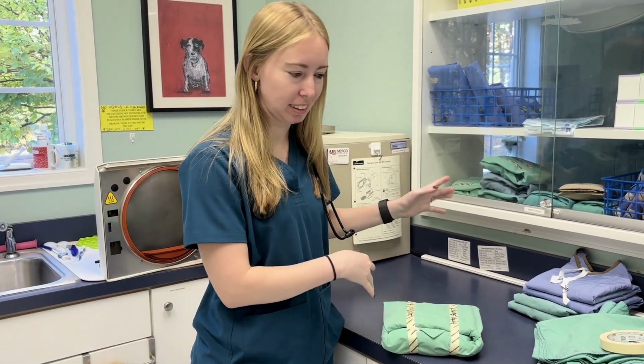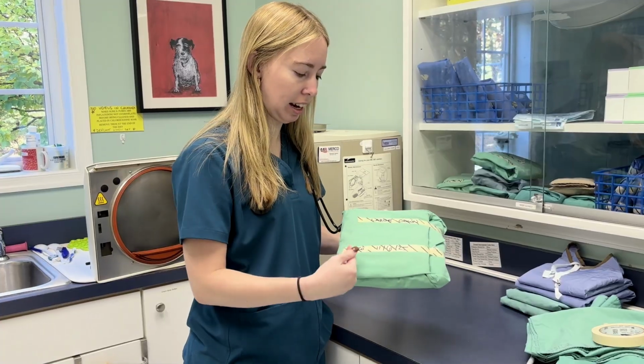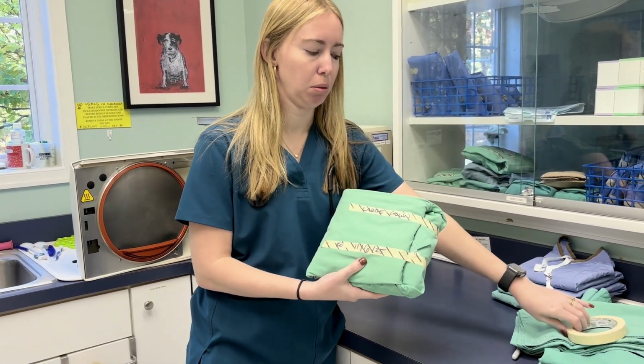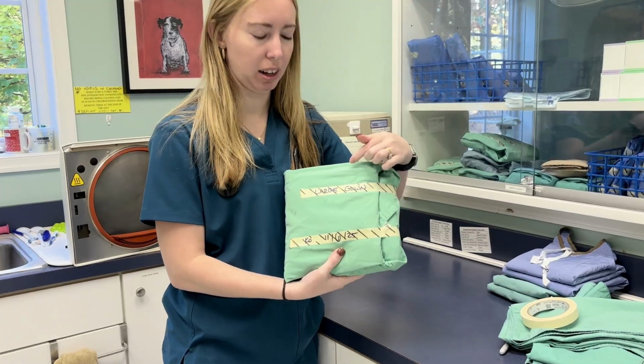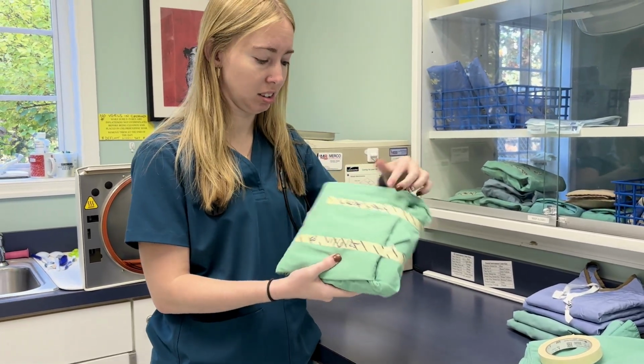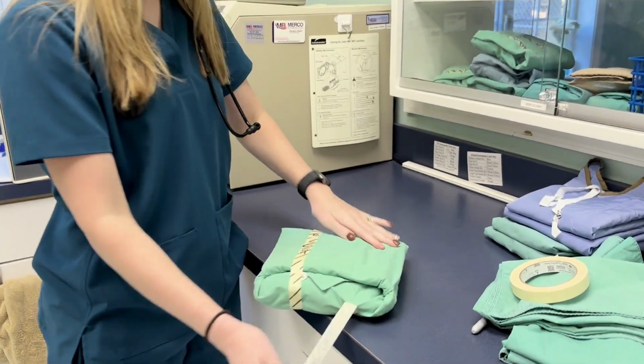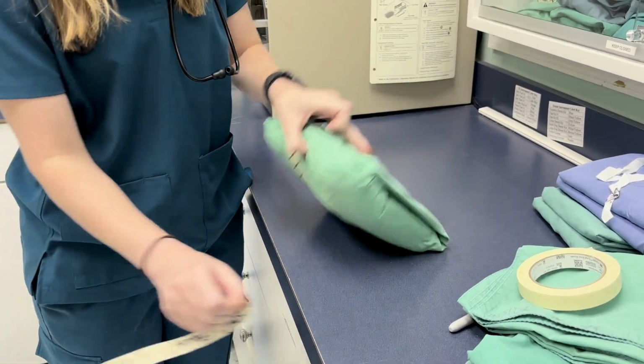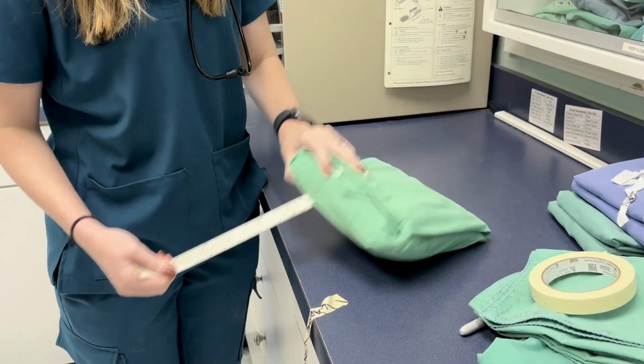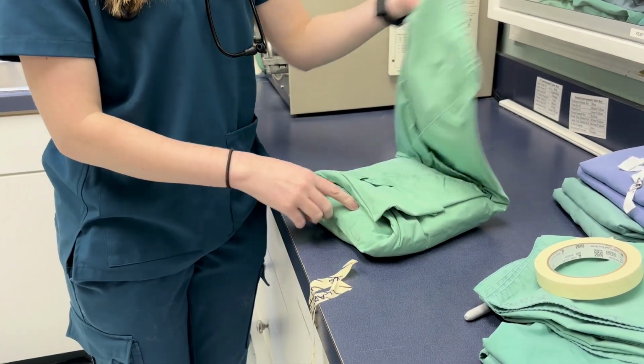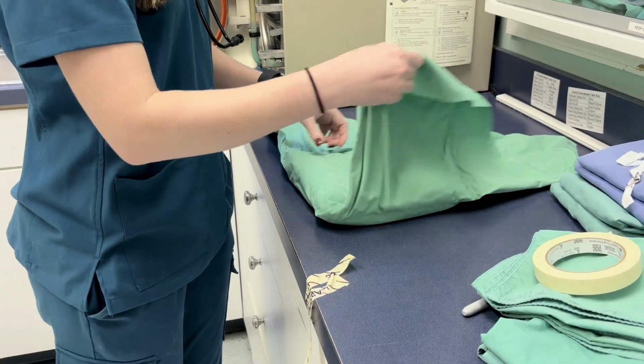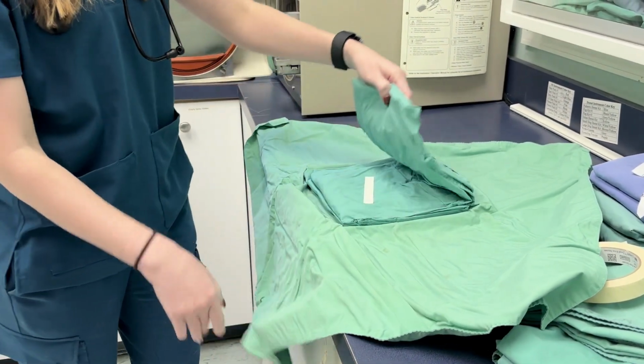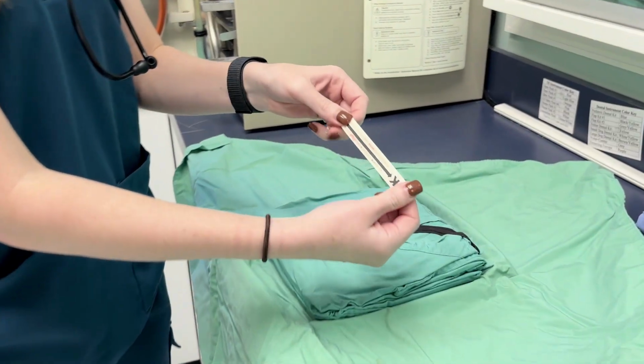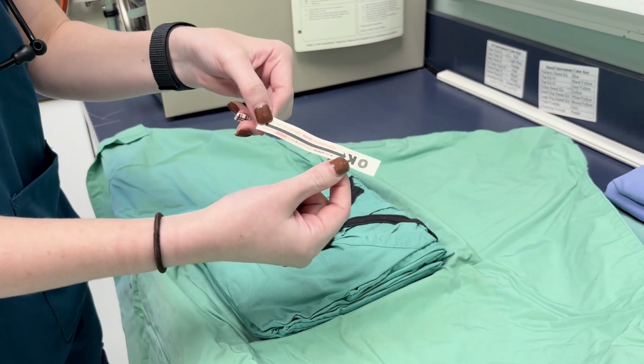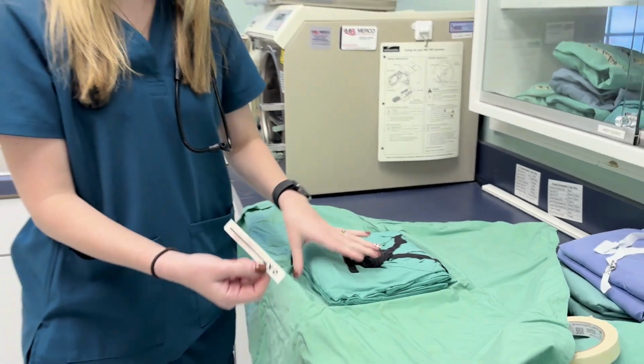And that's it. So how do we know that a pack is sterile after we've autoclaved it? One indication is the tape that we put on the outside, which originally looks like this, has black lines going across, which means that it is sterilized. Another indication is we can open this up. Earlier we had put our indicator strip inside of the pack, so we'll see what it looks like. Before there wasn't a black line, it was all clear, and now there's a black line, which means that it is sterilized. So this pack was sterilized.